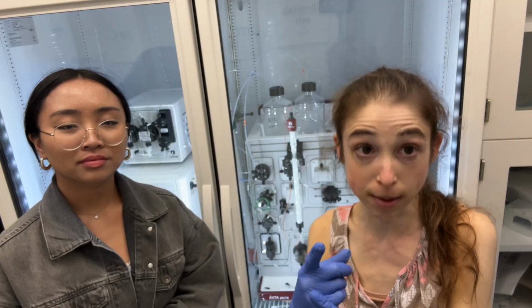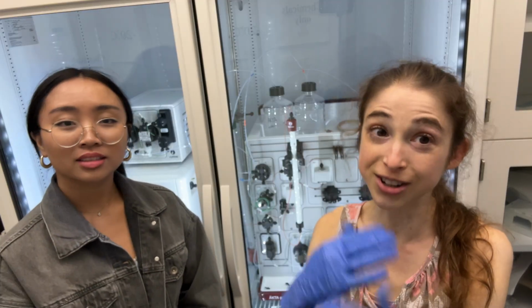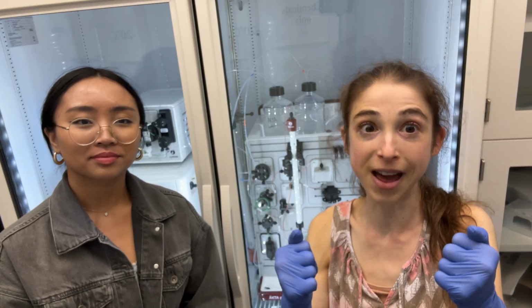That's true for both your buffers, both your pumps, as well as for your columns. So you want to wash your pump with water before you wash your pump with ethanol. And you want to wash your column with water before you wash your column with ethanol. And that is going to help make it so that you don't precipitate stuff.